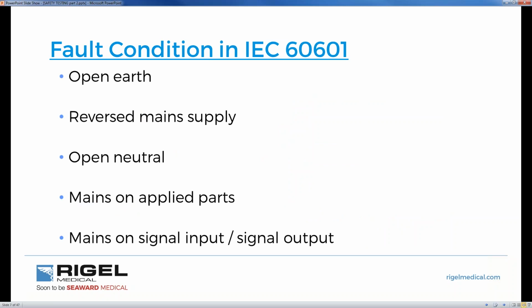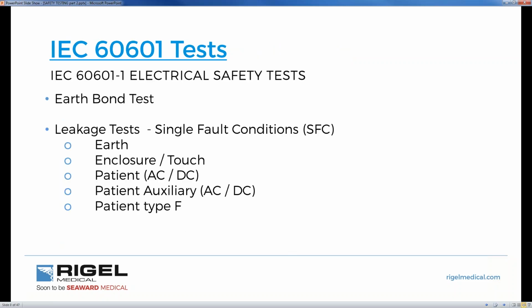60601 has various fault conditions. We have an open earth, we have reverse mains, we have open neutral, and we have mains on applied part. We also have mains on signal input or signal output, usually using the acronym SIPSOP. This test is not generally required as part of your planned performance maintenance, but it can be used in acceptance testing and in manufacturing.